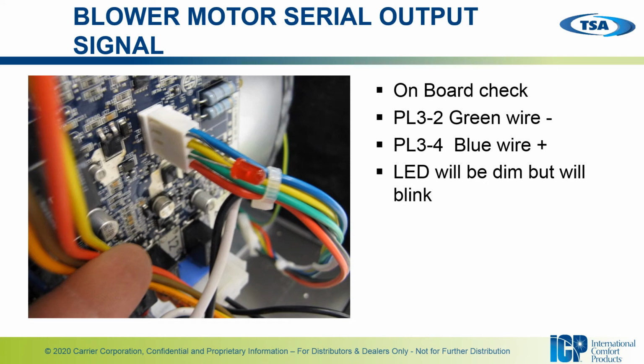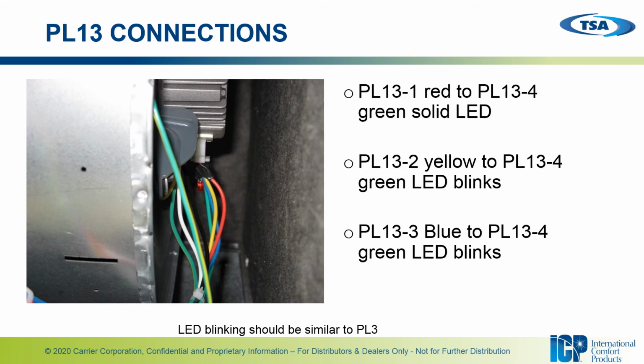Okay, and checking the blower motor serial output signal, or the feedback signal from the motor, checking between the green wire and the blue wire in the harness. It's going to be dim, but it should blink, just like checking the input signal to the control board. It's a similar signal, but much lower voltage again, but you should still be able to see that thing blink. That will indicate that the signal is there. And just like using it on the Molex plug on the board, it can also be used in the Molex plug in the motor to check the same signals, as well as check the 12 volt DC power supply.